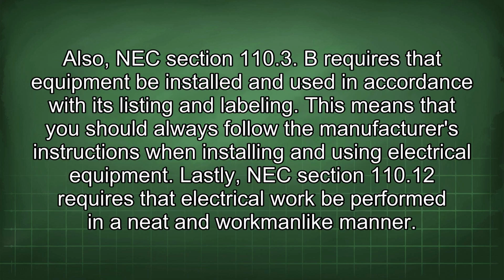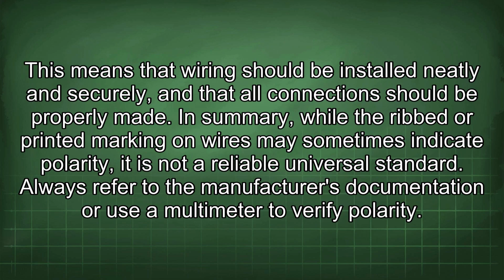Also, NEC Section 110.3(B) requires that equipment be installed and used in accordance with its listing and labeling. This means that you should always follow the manufacturer's instructions when installing and using electrical equipment. Lastly, NEC Section 110.12 requires that electrical work be performed in a neat and workmanlike manner. This means that wiring should be installed neatly and securely, and that all connections should be properly made.